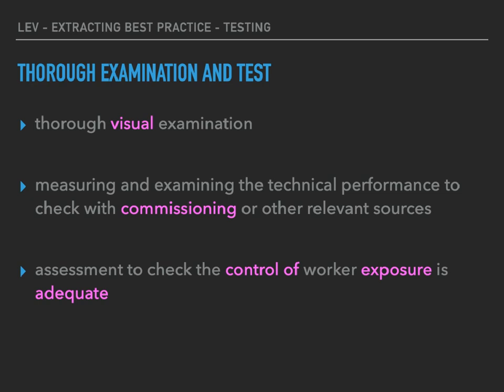You might even do smoke tests as part of your visual examination. Secondly, you measure all your pressures and flow rates, look at the technical performance of the system, and confirm it's doing what it was doing when it was commissioned. If there are any changes, why is that, and what might be causing those changes? Finally, you do an assessment to check the control of worker exposure is adequate - again, that might be a smoke test or an observation.